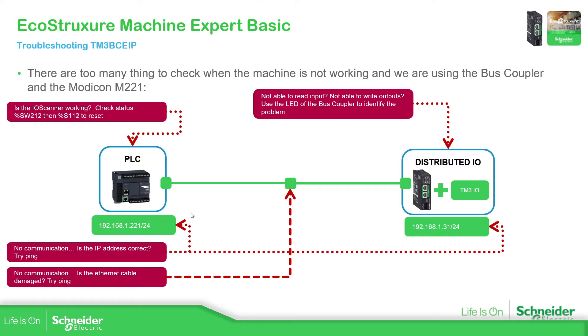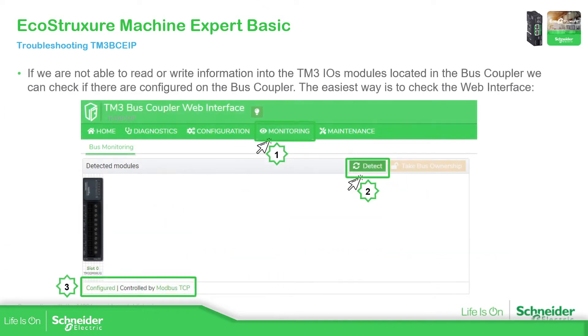The other thing we need to check is that the PLC and the bus coupler are on the same network, otherwise they are not going to talk. Then, if we don't have communication between them and the ping is not responding, you can try a different cable — probably this one is damaged. If you are not able to read any inputs and outputs of the bus coupler, you can use the LEDs in front of the bus coupler to identify what the problem is.